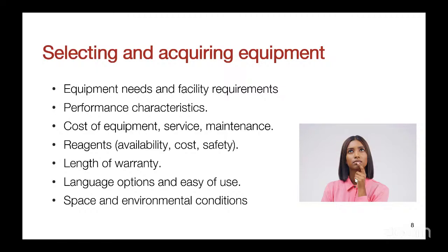There are some facilities that have bought an equipment that cannot enter the facility. The equipment is bigger than the space. And today, the equipment is lying in the corridor or somewhere else. Why? Because space and environmental conditions were not put in place.